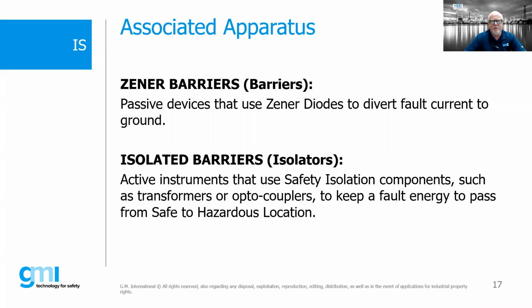So there are 2 different types of associated apparatus. There are what are called the Zener barriers. These are more or less passive devices. They're devices that will just sit there. They use Zener diodes to divert a fault condition to ground. And then we have what are called isolated barriers or isolators. Another term might be galvanic isolator. These are active devices that use some sort of safety isolation, and generally some sort of transformer or optocoupler is used on the inside of these isolated barriers to keep that fault energy from passing from a safe to a hazardous location.